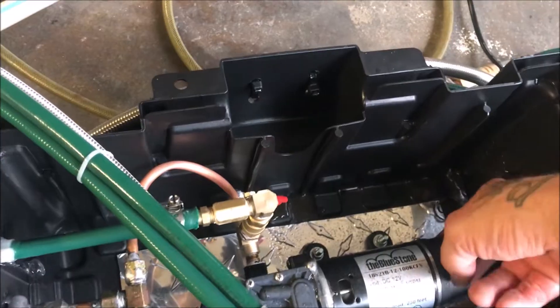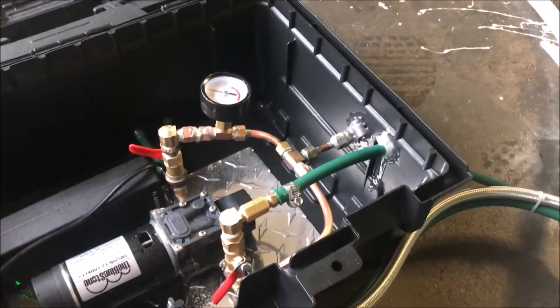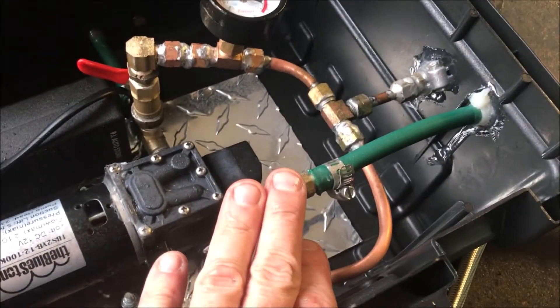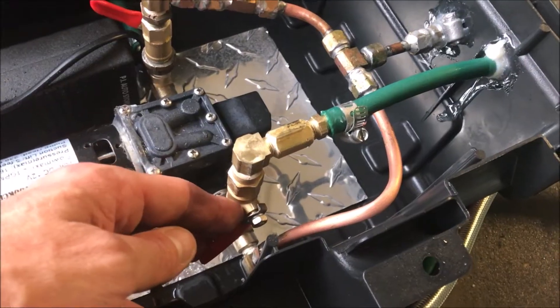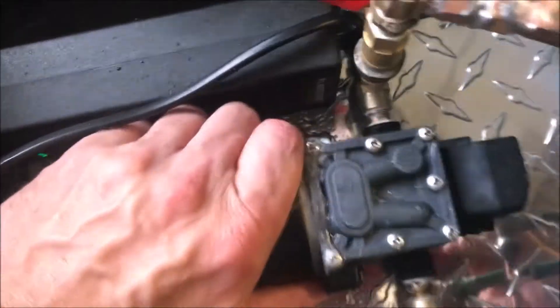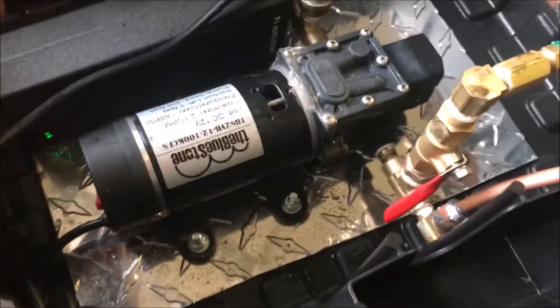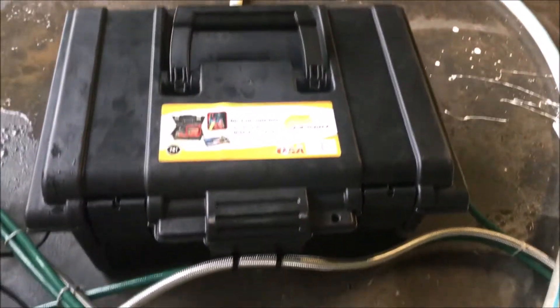Let's shut this thing down. Looks like I might have sprayed some water in there. There you have it Keith - I'm going to send this thing preset the way it is, but when you go to adjust it, it's not so much this valve you want to mess with. This is just a secondary flow rate valve - you probably leave it just the way it is. It's this valve over here that's going to control your pressure. That motor is not even really unhappy either, so we're good to go. We do not appear to have any leaks.